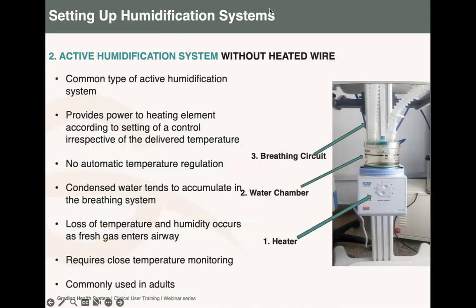Okay. So the active humidification, we said there's two types: the one without heated wire and the one with heated wire. This picture on your right shows the active humidification system without a heated wire. This is common, especially in our setting. It's a common type of active humidification system, as it provides the power to the heating element, and then the heat is controlled here at the number 1.